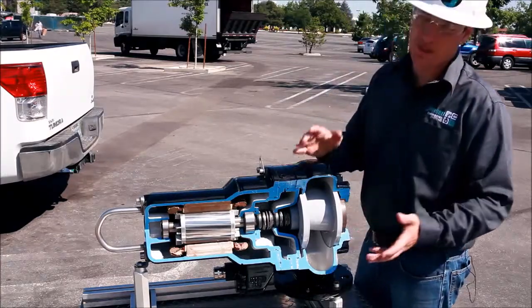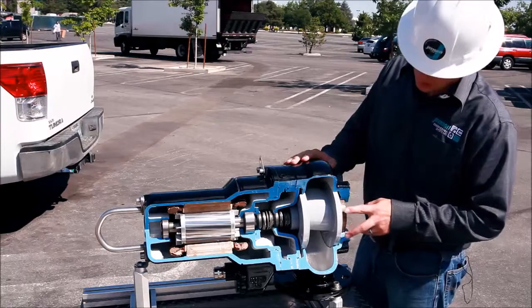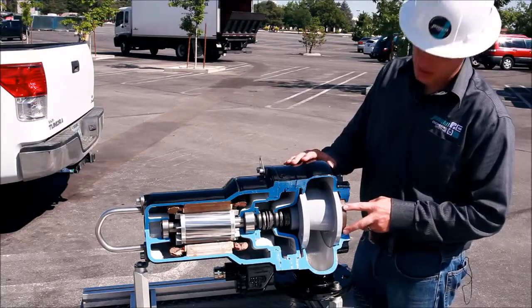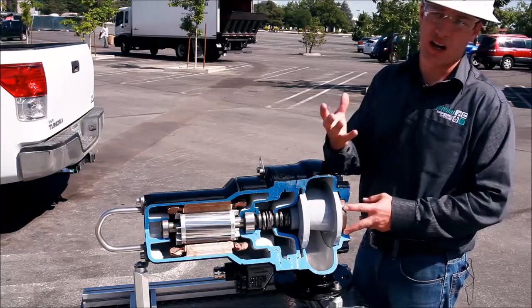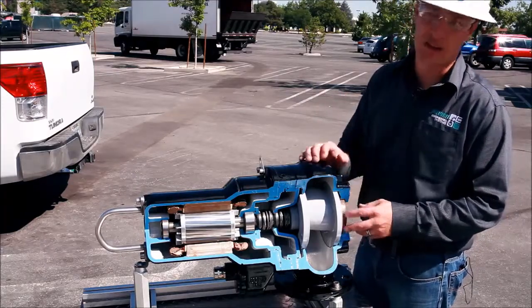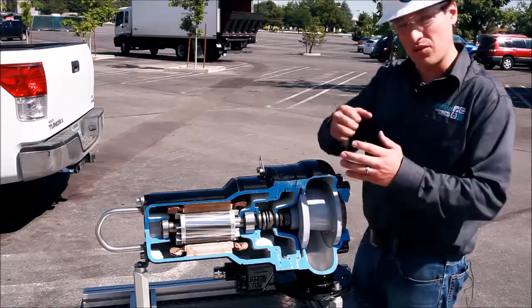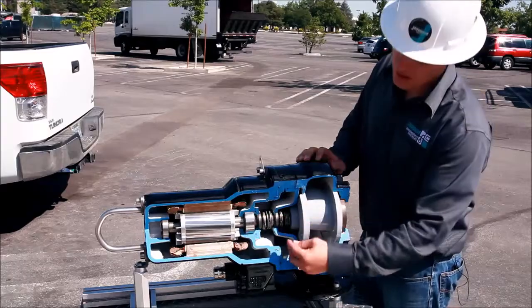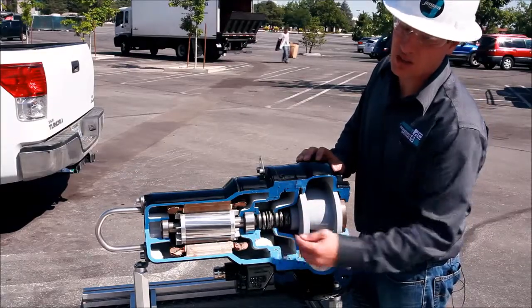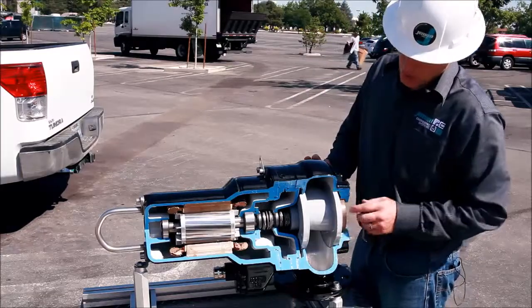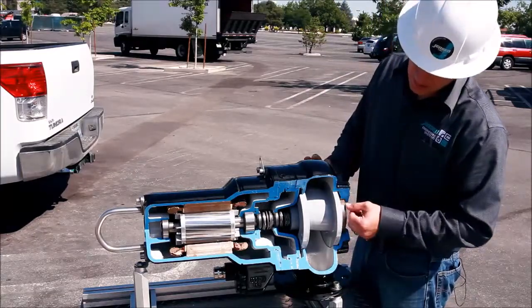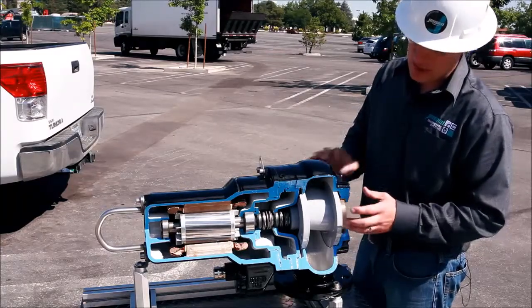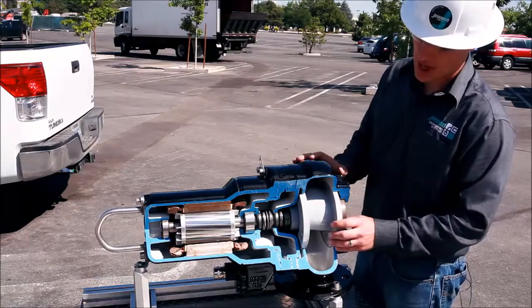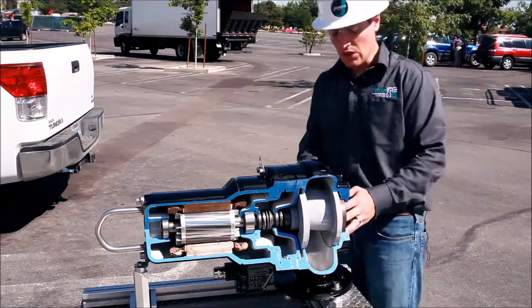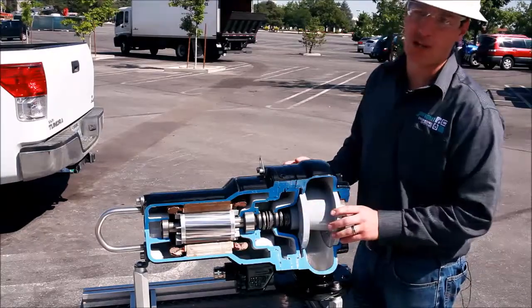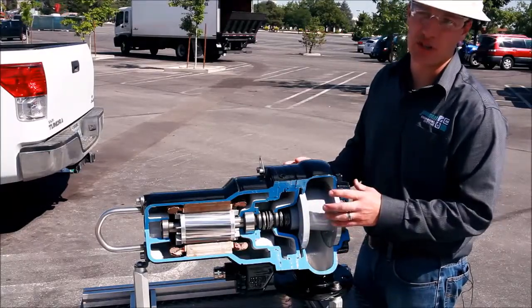Some things to take note of specific to Homa Pumps is this lower bearing wear ring. Not all pump manufacturers utilize this bearing point. What this bearing point does is, let's say you got a real big solid into the pump that knocks that volute pretty hard. It's going to put deflection forces on the pump shaft and put forces on that seal and potentially cause a seal fail. So what Homa has done to prevent that incident from happening is put a bearing point right here. This bearing point resists those lateral deflections in the shaft and therefore preserves the life of the pump. So again, this volute right here, this is the wet chamber. This is where all our sanitary sewage is being pumped through.